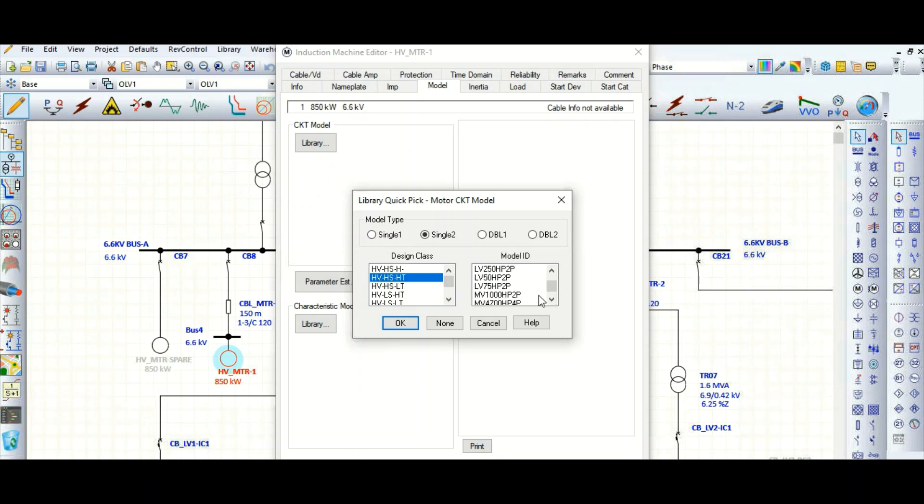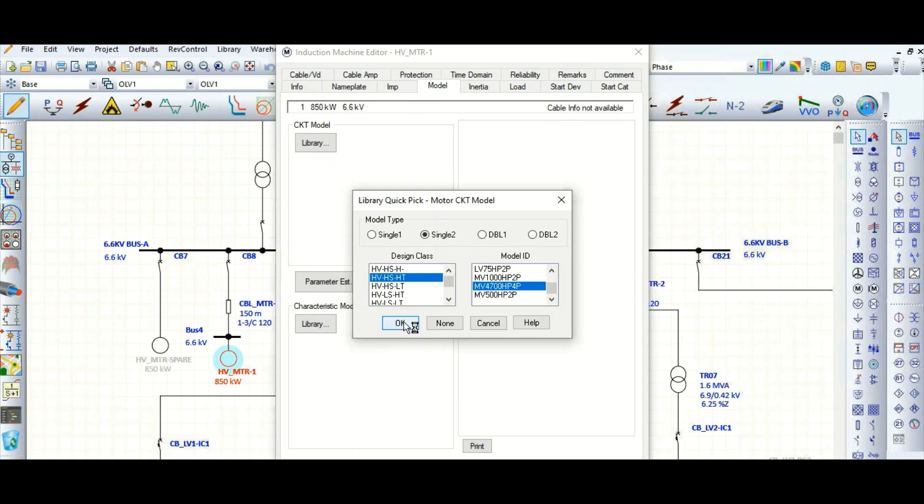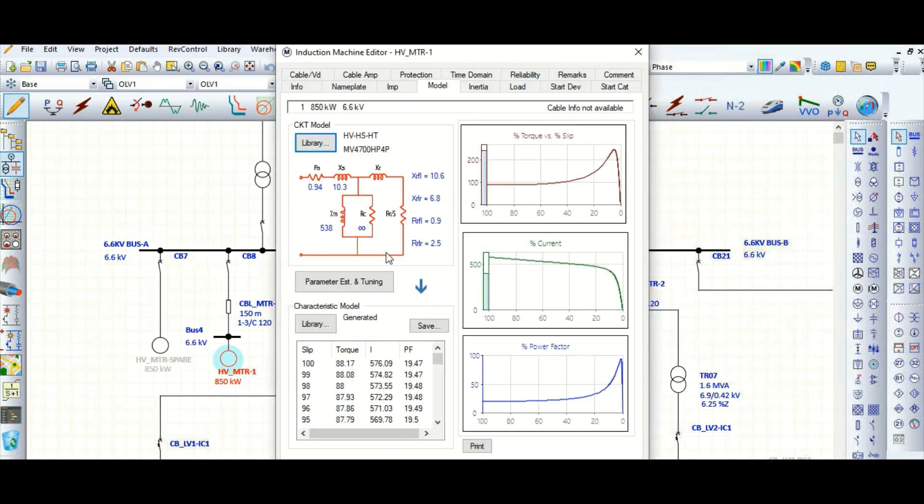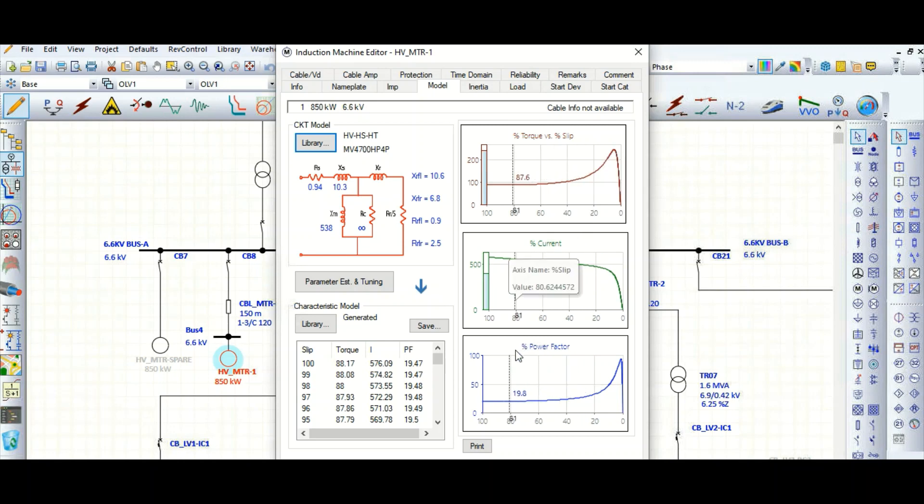Let's consider this single cage motor for high speed, high torque. If it matches with your project requirement you can select here - this model ID medium voltage 4700 HP four pole motor. Click OK to select and update. Now you can see these are the parameters already calculated by ETAP, and this is the torque speed curve, current, power factor.